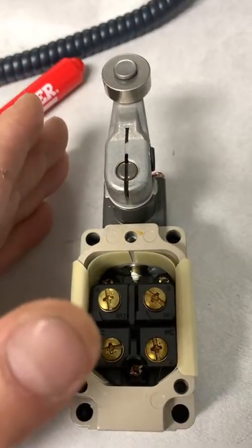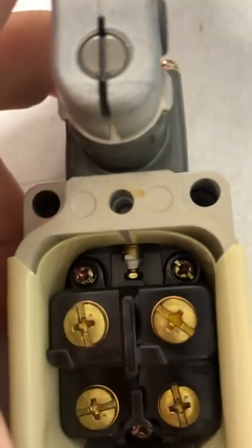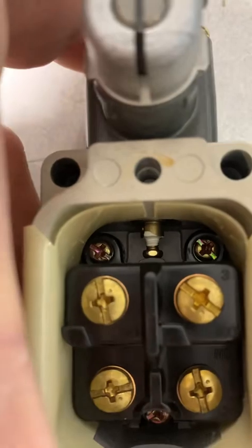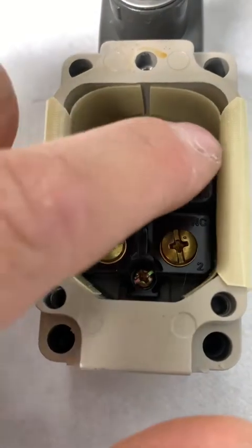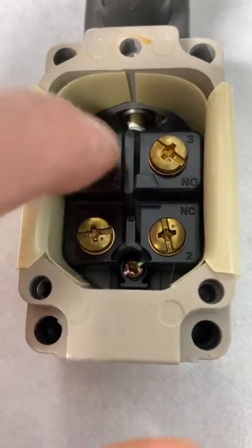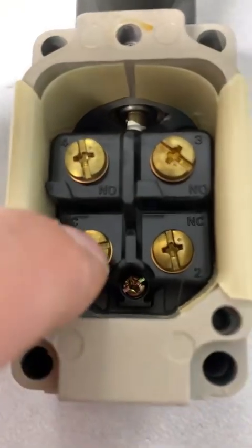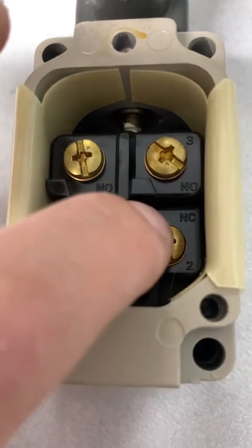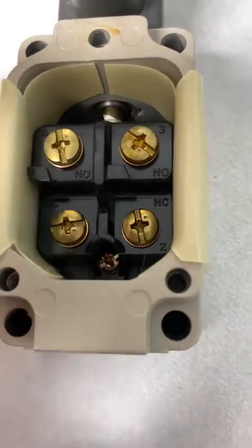And then when an object or something would come in contact with the actuator arm, you will see that this plunger here is going to switch. It's going to make contact with the switch, and then now your normally open set of contacts will close. So now there will be a path for electricity to get from here to here, and your normally closed set of contacts would open. So it would open and cut continuity. No more electricity can pass through here.